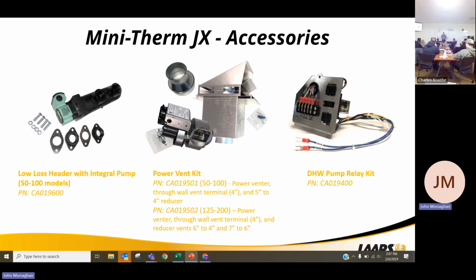One of the advantages of it is I can get this blower kit installed in that joist bay as close to my exit point as possible. So now I can run my single wall galvanized or single wall flue piping from my boiler to there, much cheaper than my AL29 4C stainless. And maybe only have to have a small section of AL29 4C to get out for my termination. Again, when we're looking at these products and we're competing against other companies, controlling our costs is going to be key in winning us those bids. And when we have a compromised chimney where we can't vent up through that, that sidewall vent kit's going to make it much easier.